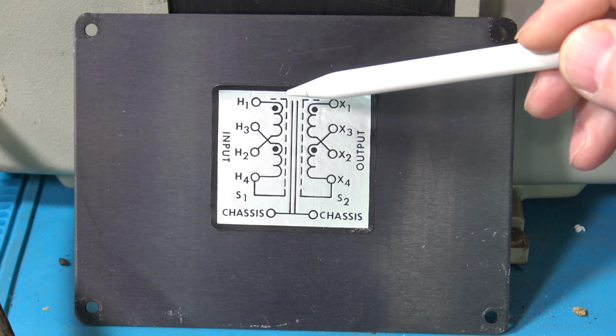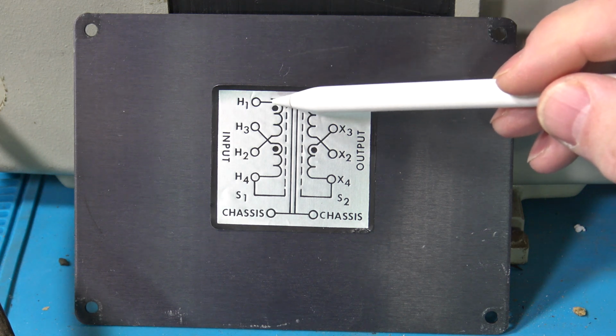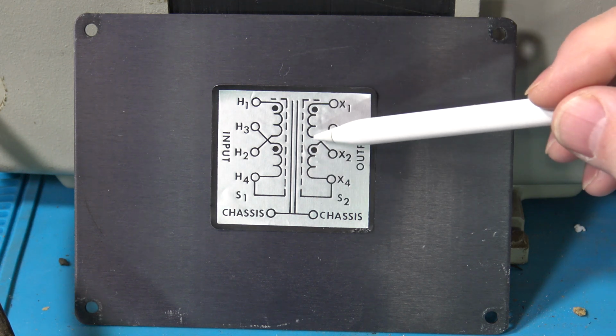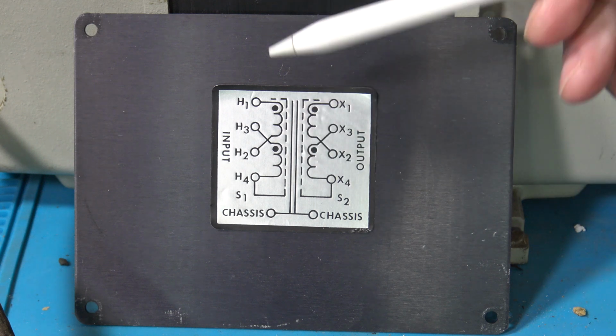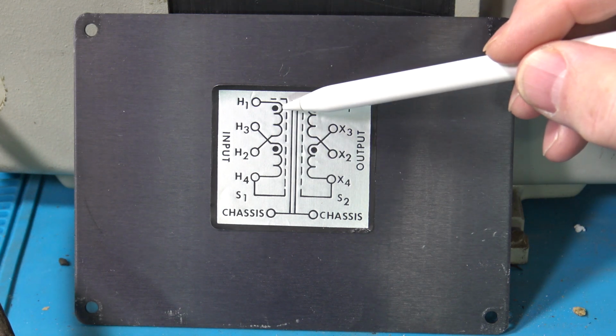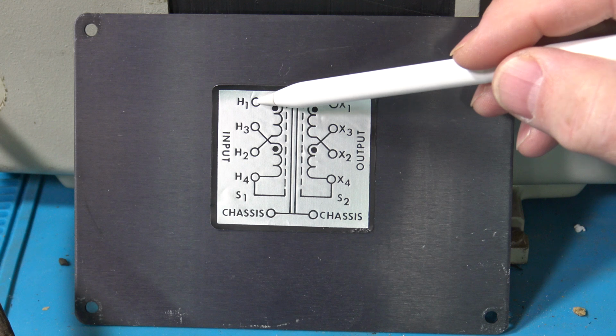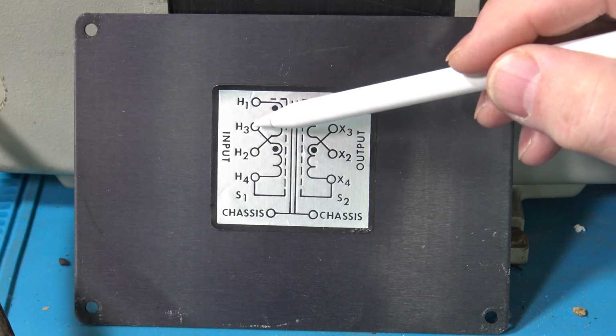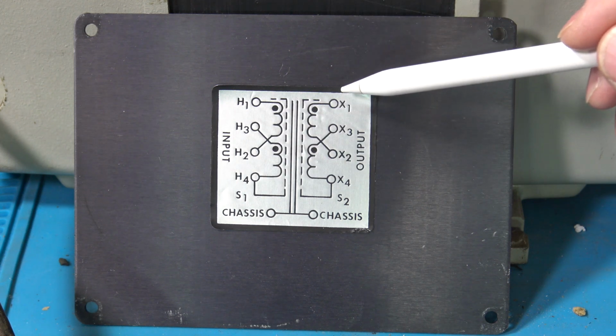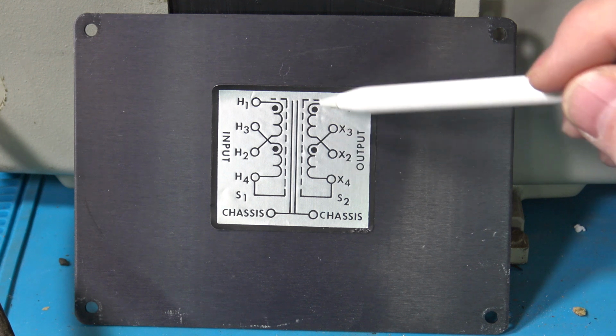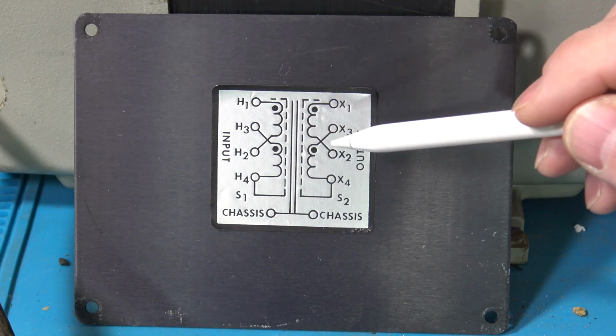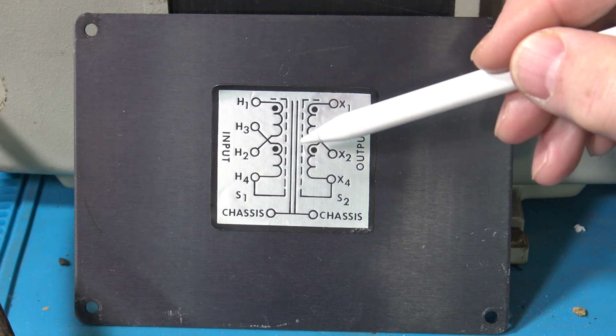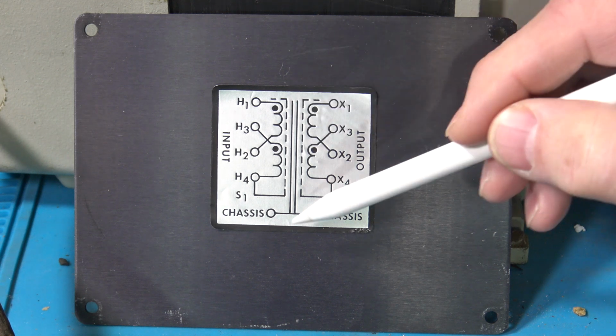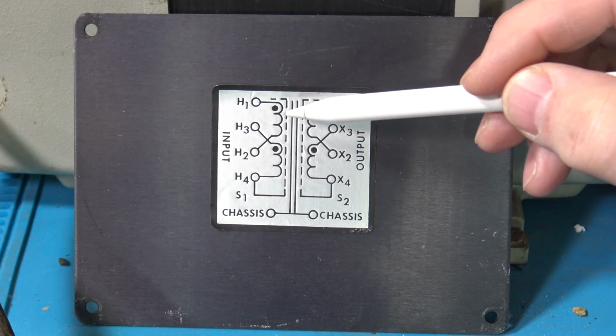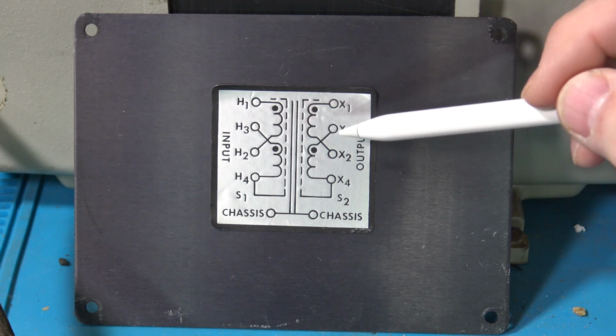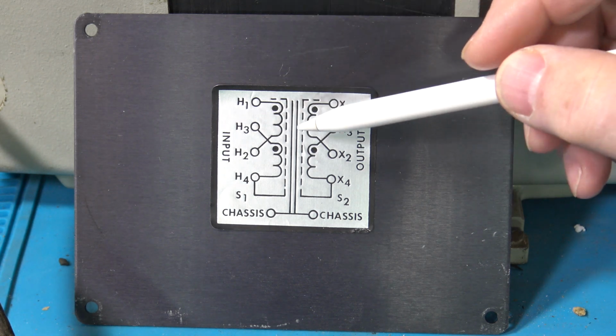All right, guys, so what we're going to do is, first of all, check to make sure that each winding is still a winding, that it hasn't been opened because it was burned open or something from some kind of fault. So we'll ohm H1, H2, make sure that winding is still intact. Same with H3 and H4, and X1 and X2, and X3 and X4. So we'll make sure that the windings are actually still there, and that the ohms look like they should. They all should have essentially around the same ohms, right? So it's a 1-to-1 transformer, so they all should have the same turns.